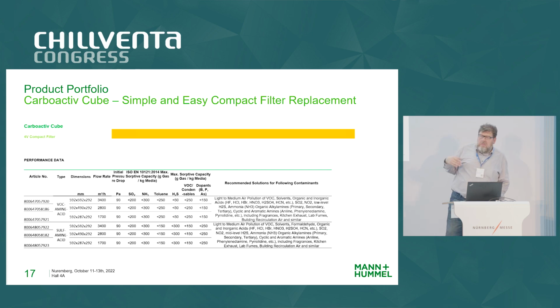The cost. That depends on the systems. It's how polluted your air is, how often you have polluted air. That can be from replacing a simple V-bank filter, a few hundred euros, up to the point where you have to invest in an industrial installation, including a new housing and so on, that can be a few thousand. But then we're talking about heavily polluted places like, for instance, refineries, tire manufacturing, pulp and paper mills, chemical facilities, wastewater plants. These are the ones that have to really heavily invest, because then you generate tons of pollutants on site, very close to your electrical installations.